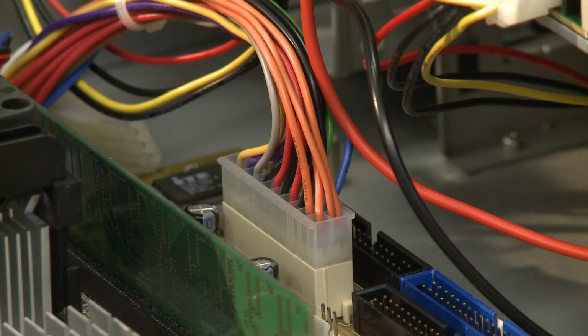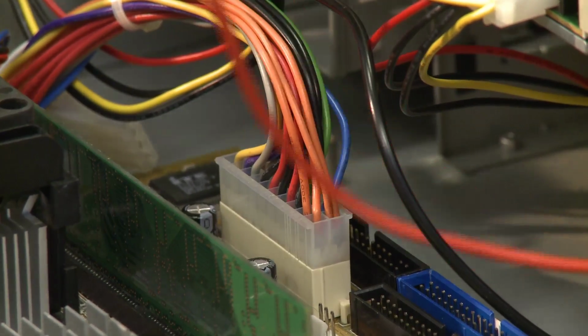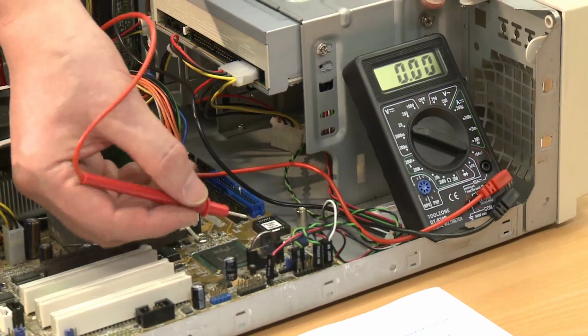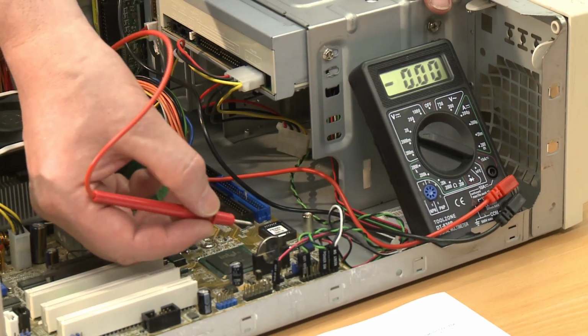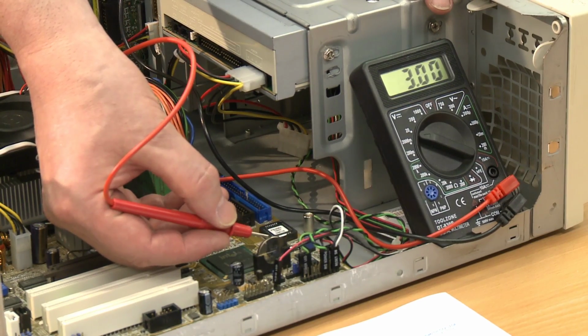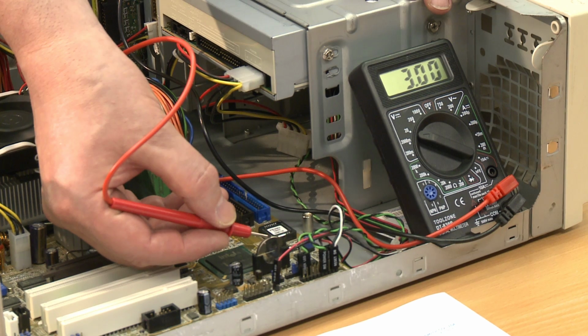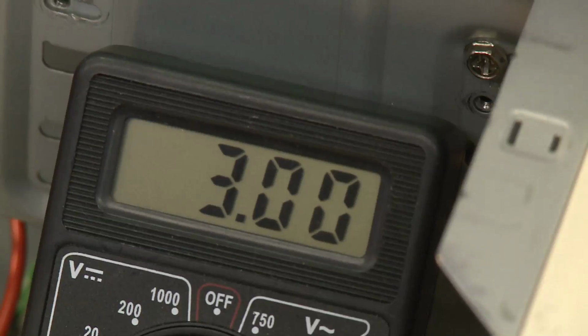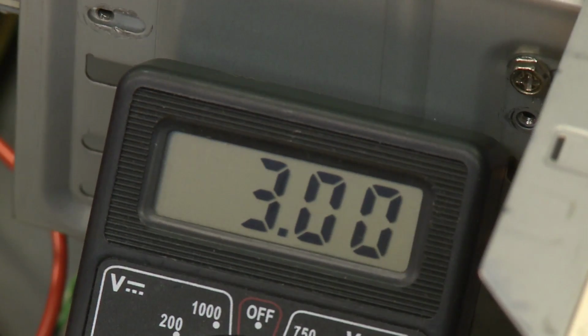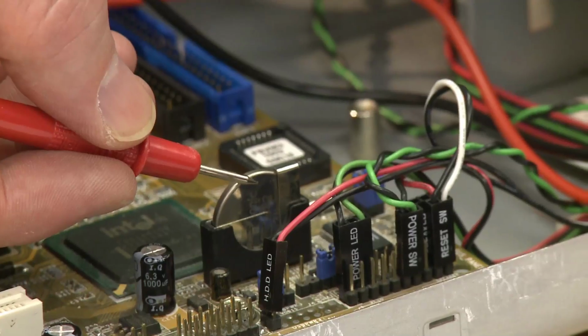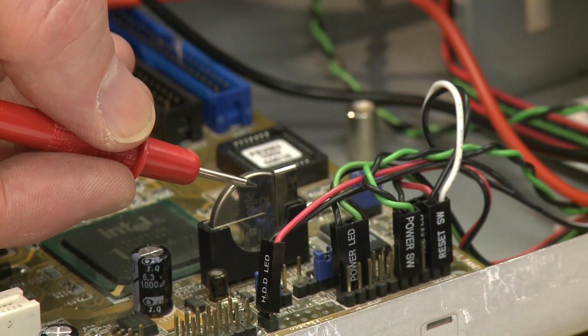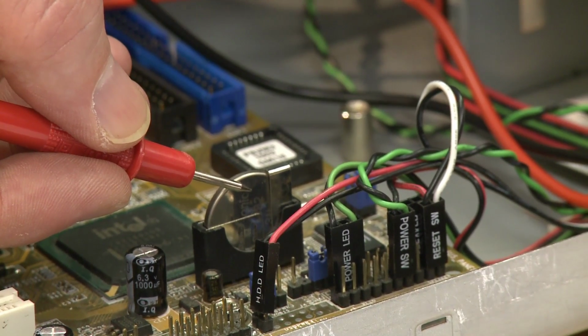While measuring the power supply and you still have the meter connected, it's worthwhile taking the chance to measure the battery, which is very important to the startup process. Just by touching the outside of the battery, we're looking for a reading of approximately 3 volts. If it's much lower than 3 volts, then you should replace it.